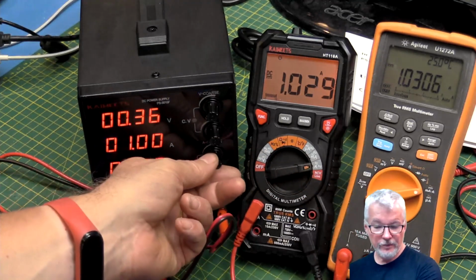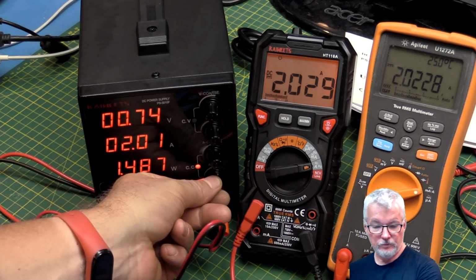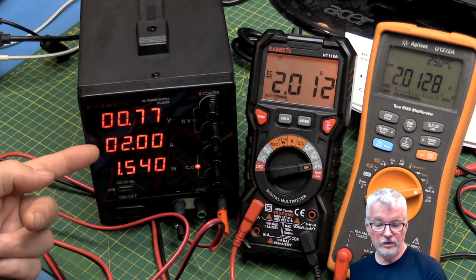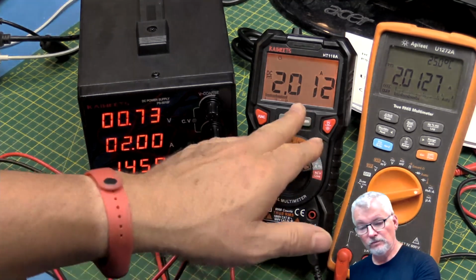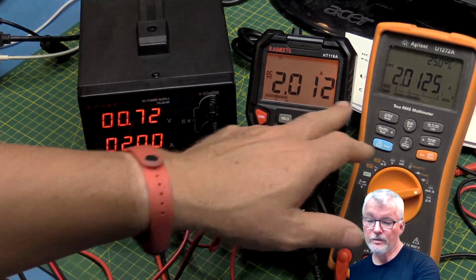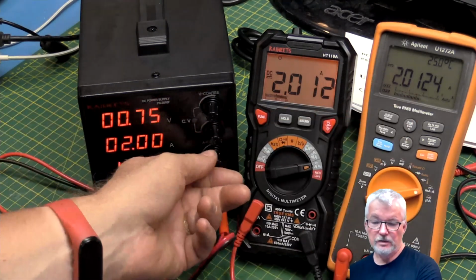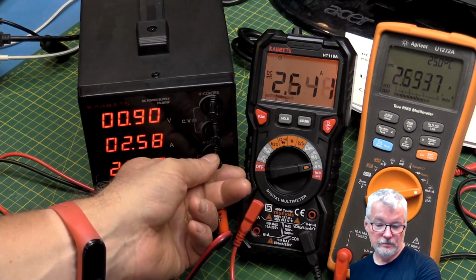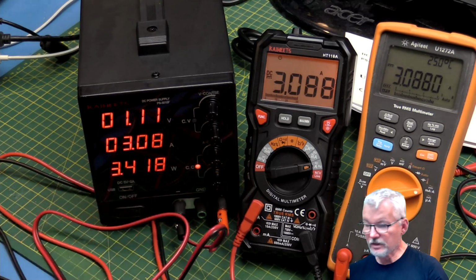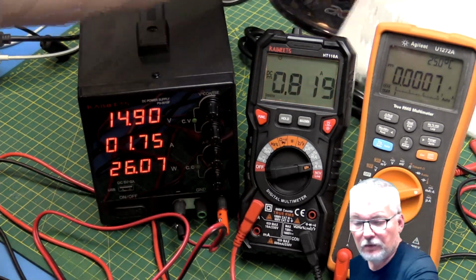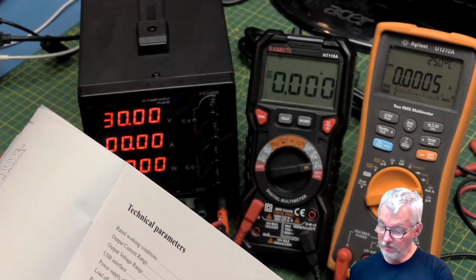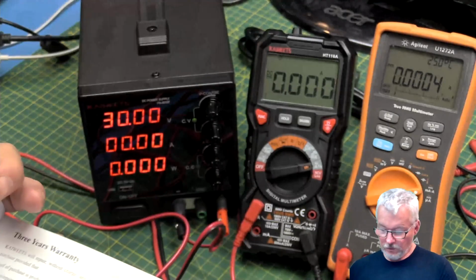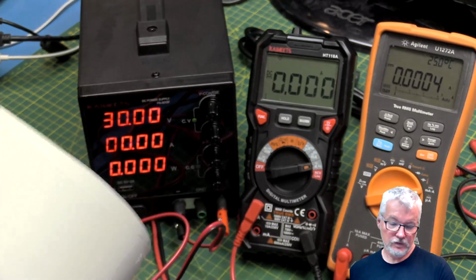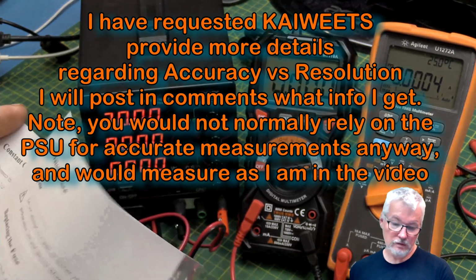Let's take it up to 2 amps. So that's 2.00 here, 2.01, so it's within 1%. What does it actually say for the accuracy of the meter? Display accuracy, plus or minus 0.1%. Is that voltage and current? The voltage is certainly working for that accuracy. Actually, it doesn't say whether it discriminates between the two of them.